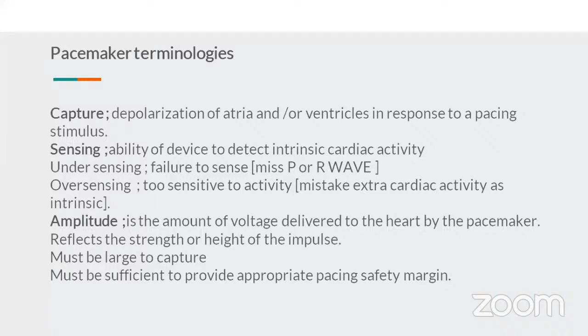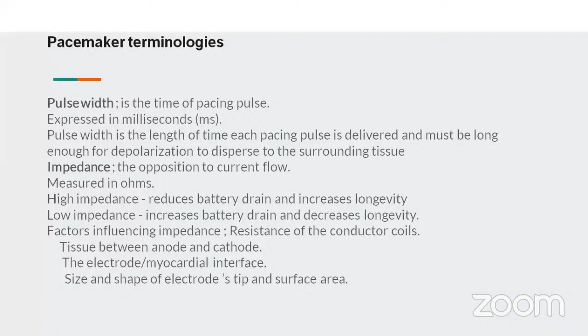It is usually expressed in milliseconds, whereas impedance is the opposition to the current flow. It is measured in ohms. High impedance reduces the battery drain and increases the longevity, whereas low impedance increases the battery drain and decreases its longevity. Factors influencing impedance are resistance of the lead coils, tissue between the anode and the cathode, the electrode and myocardial interface, and the size and shape of the electrode tip and its surface area.